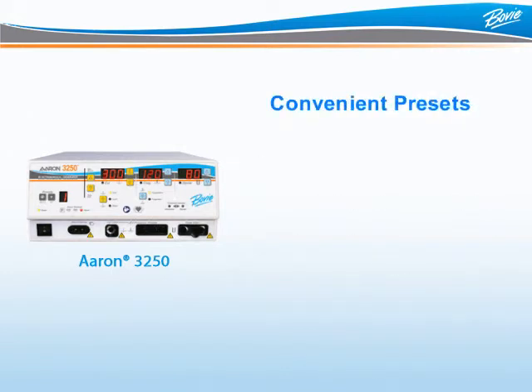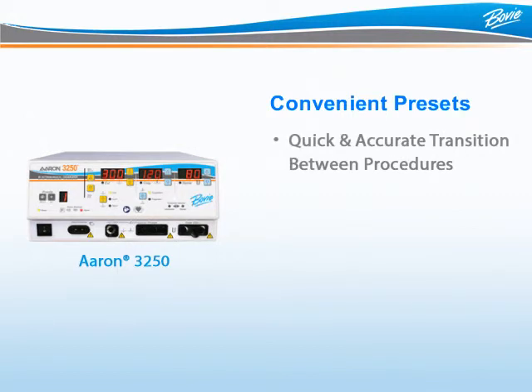Surgery centers and hospital ORs are extremely busy and transitions between procedures must be quick and accurate. To assist, the Aaron 3250 offers 10 automatic presets, which can be set up for the 10 most common procedure power settings.